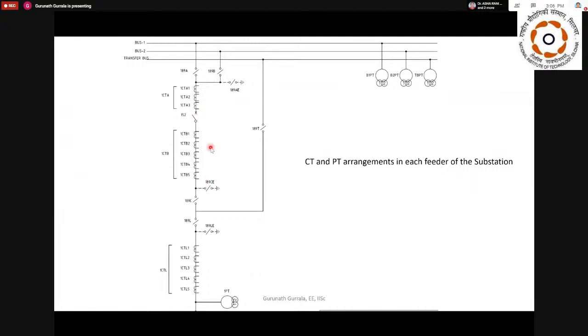When I say in the previous diagram there is only 1 CT or 3 CTs, each CT will have different secondaries, maybe 1 for metering and 2 for protection, depending on the scheme that you have. So to realize it, it is not a single CT essentially, it is actually 3 different secondaries that have to be there. But making a CT which has 1 primary and multiple secondaries requires significant money.